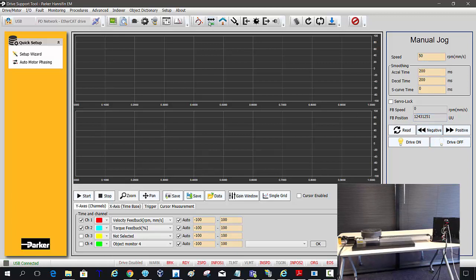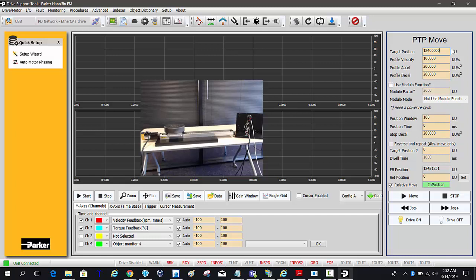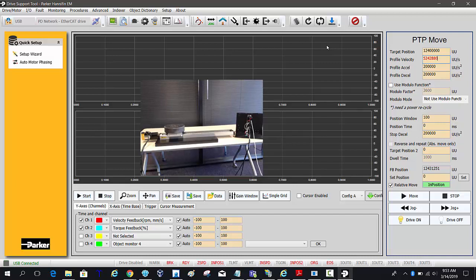So if I go into the point to point move I'm going to start at that position. Now it's 524,288, so if I do 524,288 that would be one revolution per second. Fairly long travel so I'm going to go ahead and put a zero on there, so that would be 10 revolutions per second.